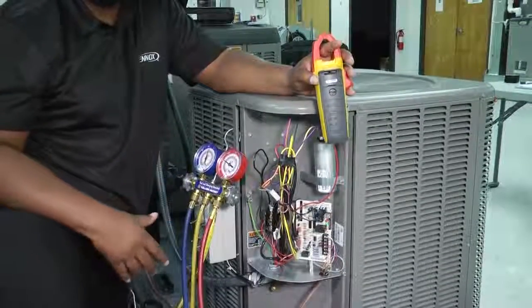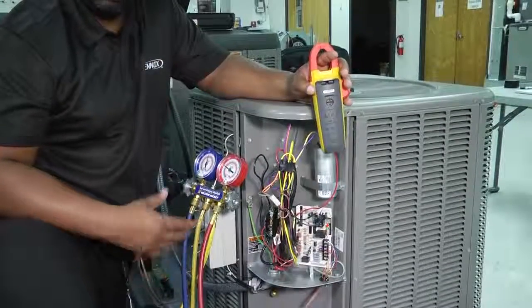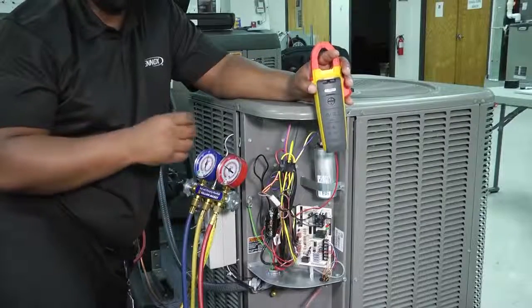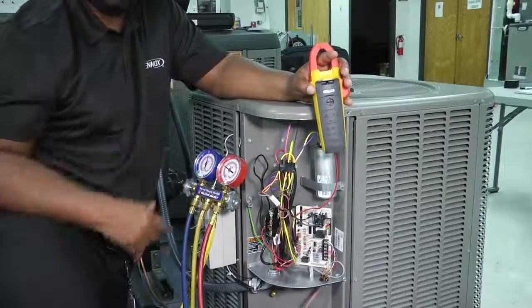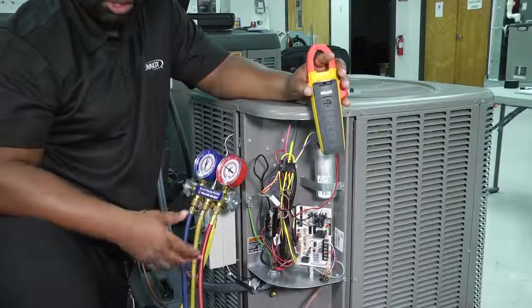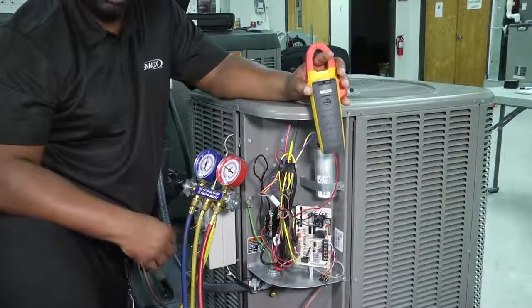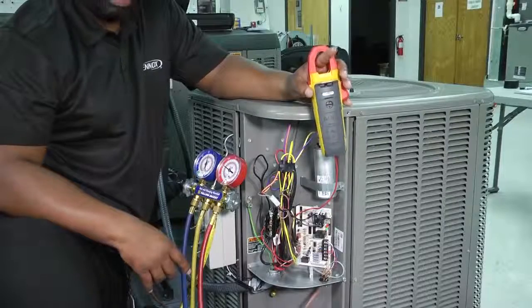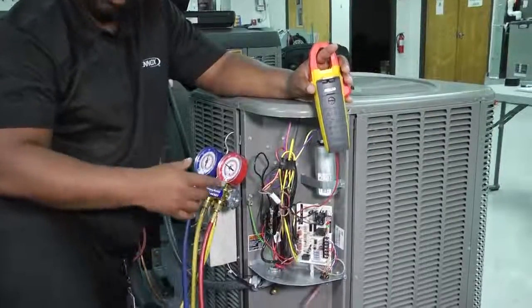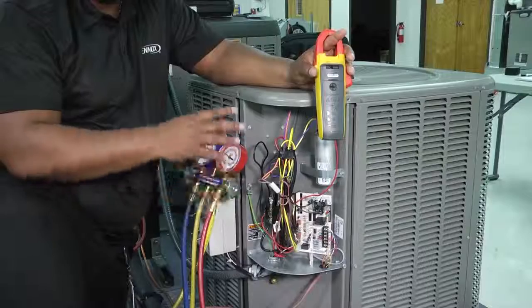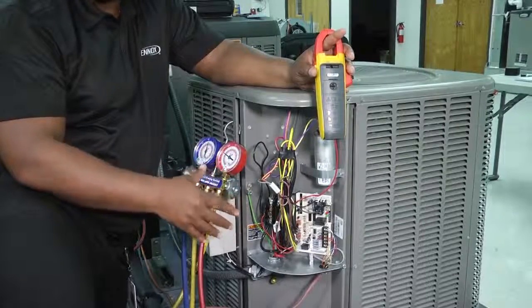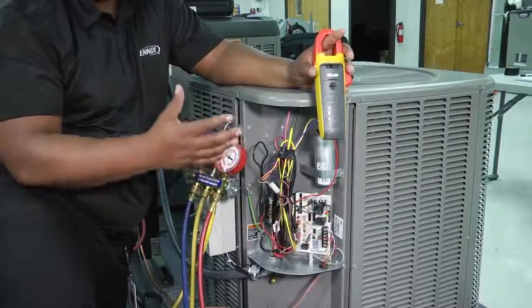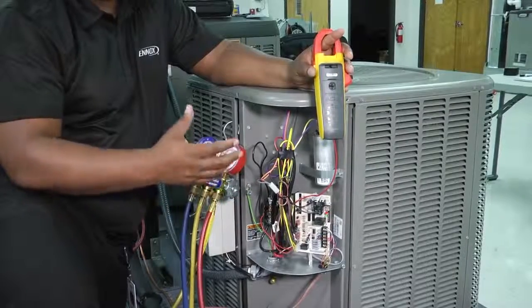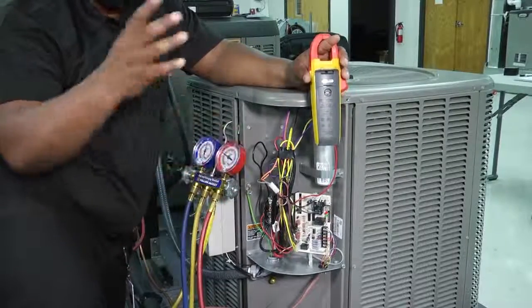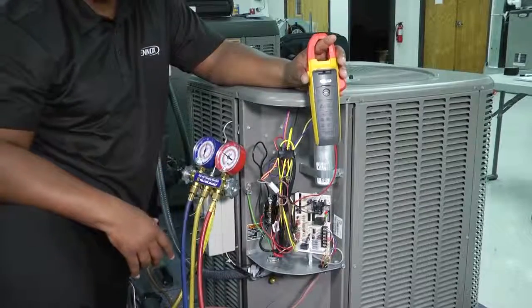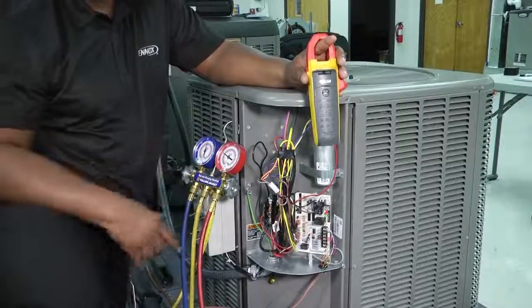We can take our superheat number and our subcooling numbers and make sure that they are within tolerance of manufacturer specs to ensure that our unit is operating at maximum efficiency. One of the things that you have to check is when it comes to subcooling, sometimes on the data plate, it'll tell you what that range, that number should be. It'll say plus or minus 3 degrees subcooling or plus or minus 4 degrees subcooling, right? So you want to make sure that when you get your subcooling number, you're there. The same thing with our superheat.